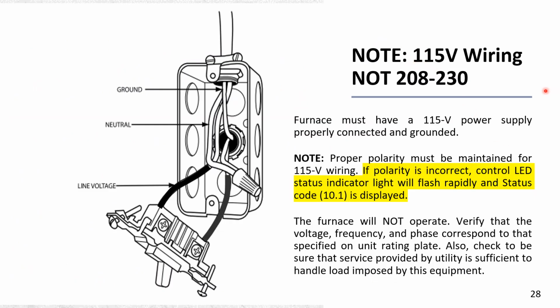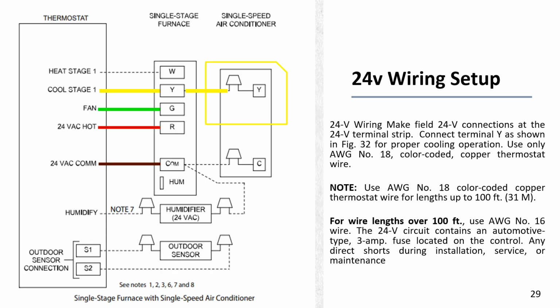Also, too, on this, the 115 volt. Now, this is something that I've not seen a lot of people mention, but as you can tell, they want you to break the power, the line voltage there at the furnace with a power switch, and make sure you have proper polarity. Basically, on 115 volt means you got to have good ground. If your polarity is off, you'll have a 10.1 display on your LED control board, and that just means you don't have a good enough ground or good enough connection on your wires. So make sure all the wire nuts are tight. Everything's tightened down on every piece of equipment you get.